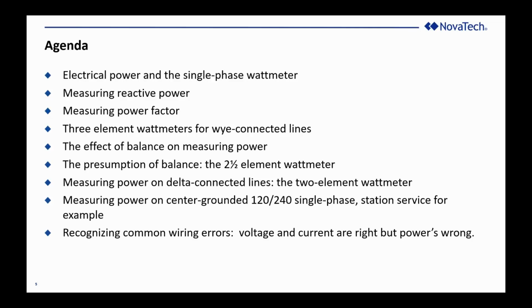One of the tangents is the way that a 2-element wattmeter can be used for center grounded 120/240. I know most of the attendees today aren't so much interested in measuring residential power, but we often get requests from customers on how to use our meters in a substation to look at the station service power. And I think that's an interesting example, so we're going to talk about that for a couple of minutes.